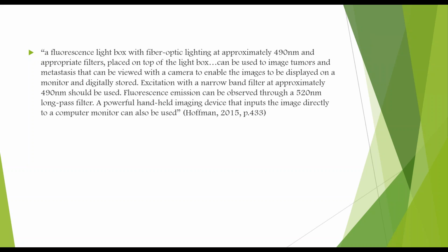Excitation with a narrowband filter at approximately 490 nanometers should be used. Fluorescence emission can be observed through a 520 nanometer long pass filter. A powerful handheld imaging device that inputs the image directly to a computer monitor can also be used.